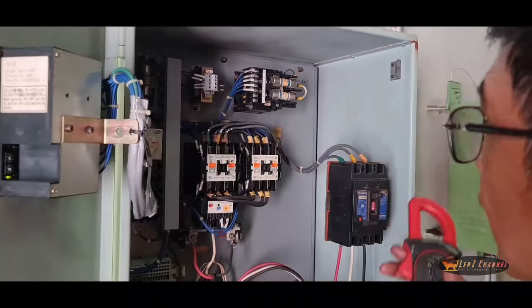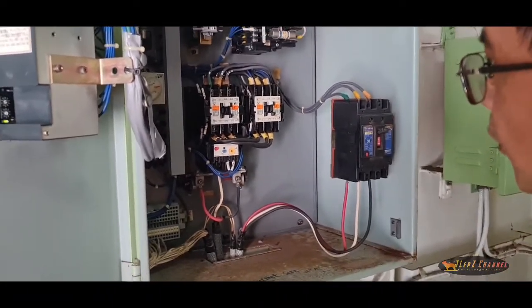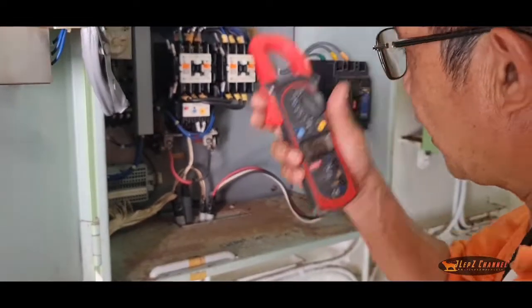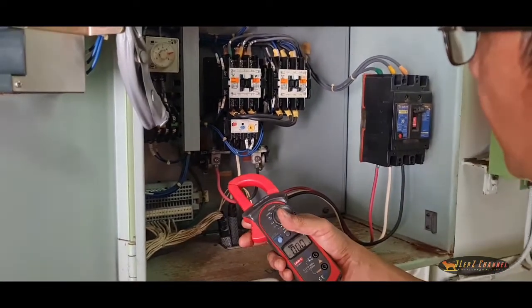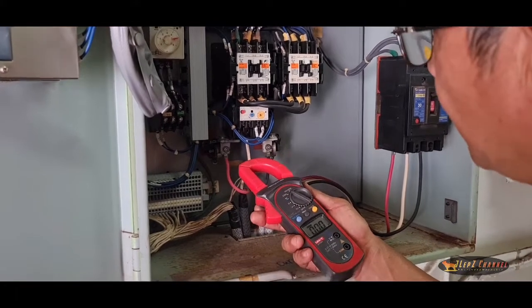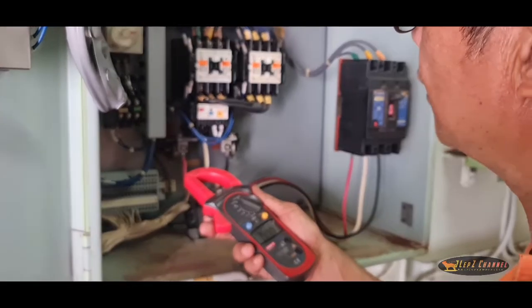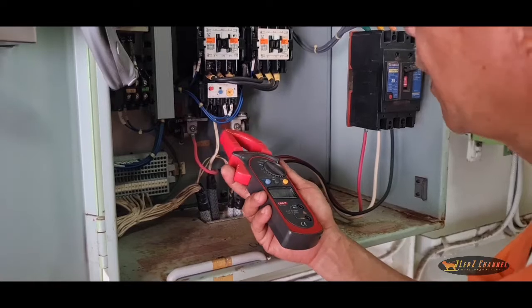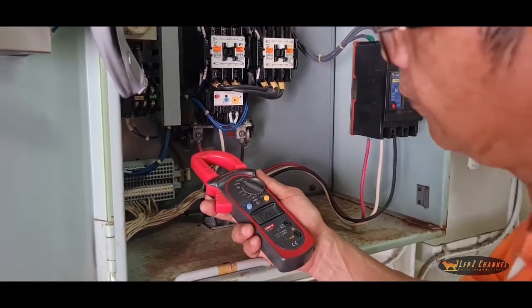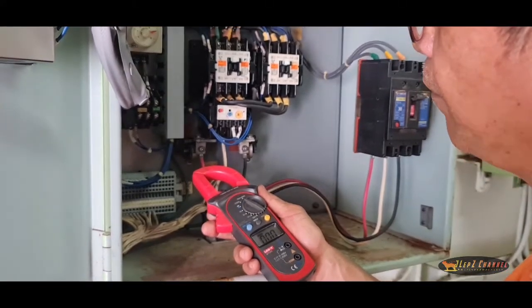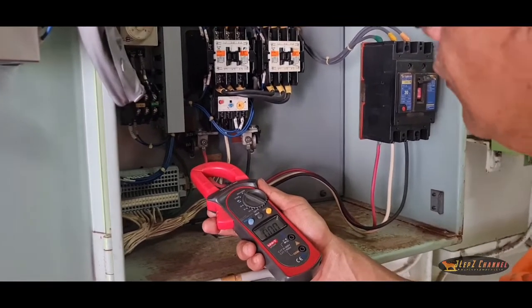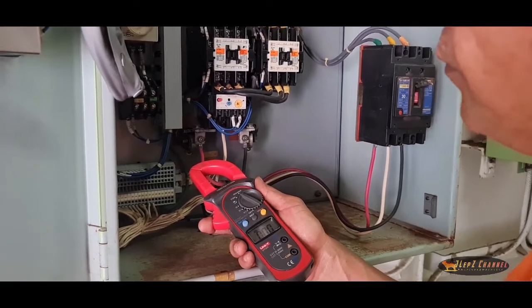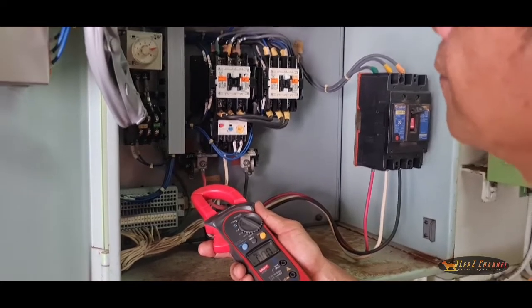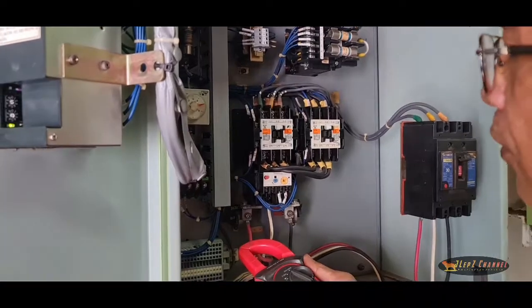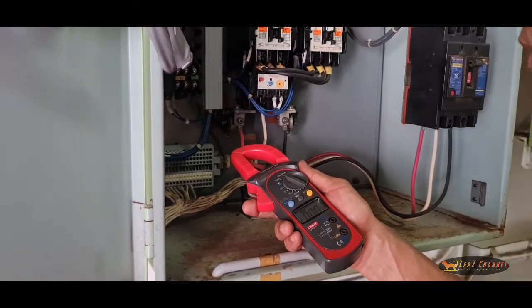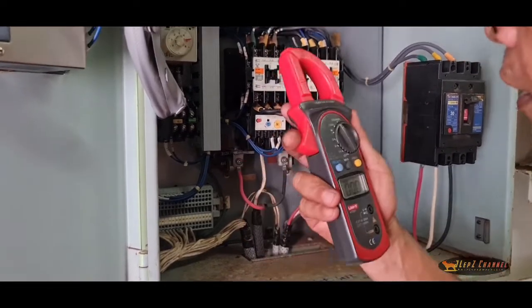Now you see, this is the control panel of the engine room fan. The purpose of using this is so that you, not just by knowing the line current, know where to apply this knowledge of the clamp tester with regards to the setting of the overload relay of the engine room fan. Otherwise, if there is no nameplate where the full load current was stated in the motor, and aside from that, if the motor was located in a hazardous area, how could you know the nameplate current or the full load current? So the best way is by using the clampmeter.